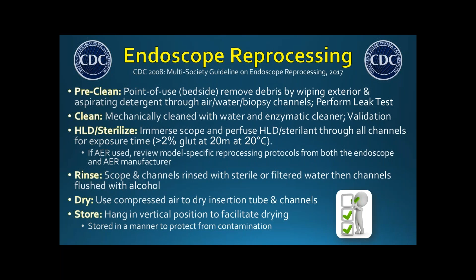There's a lot of advantages to using those. They take away a lot of the potential errors that come into the manual cleaning process. They increase the efficiency and the reliability of the high-level disinfectant. It's able to do everything it needs to do in a very systematic way. And it definitely reduces personnel exposure to chemicals, especially if you're using peracetic acid for your high-level disinfectant. Those are very strong smelling chemicals. Also, with the AERs you're using filtered tap water, so it doesn't have as many minerals.